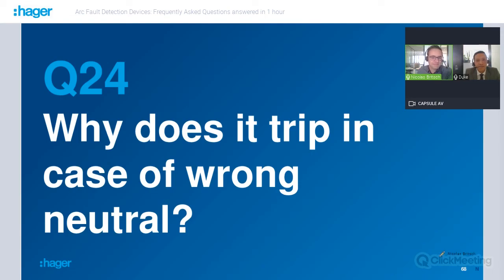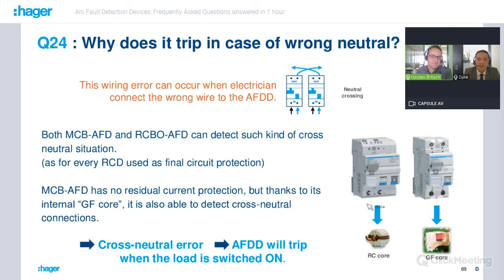It's clear, thank you. Okay, now a question for you, Duke. Why does it trip in case of a crossed neutral? Okay, this question we already saw when you explained the composition of our AFDD. The wiring error can occur when electricians connect the wrong wire to the AFDD, neutral crossing. In our AFDDs, we can detect such a cross neutral situation, as for every RCD used in final circuit protections. So with a cross neutral error, the AFDD will trip when the load is switched on, thanks to the RC core and the GF core.